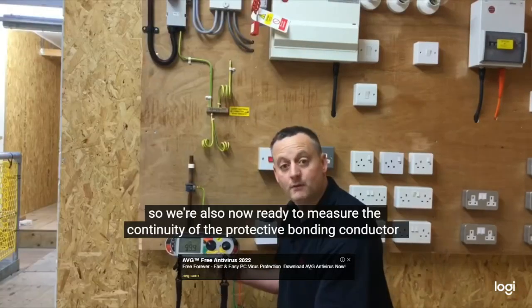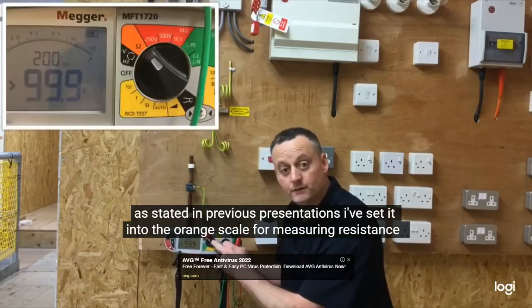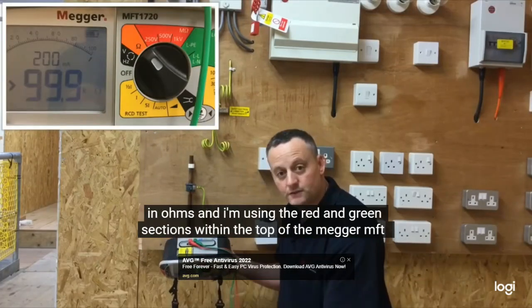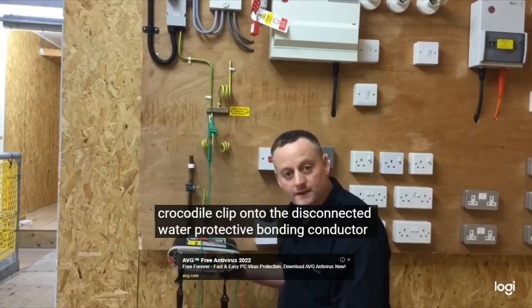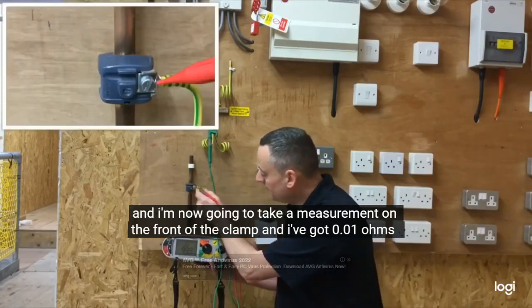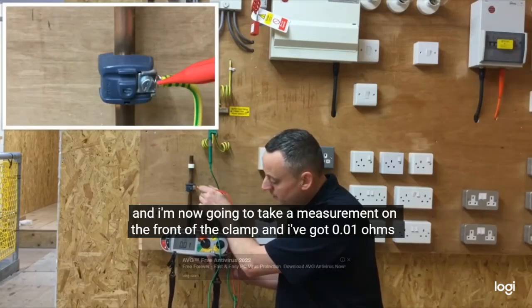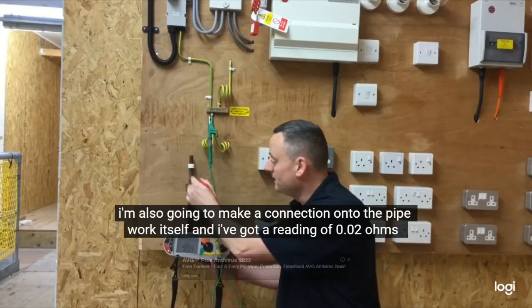Let's see how we're going to carry out the test. So we're all set up now, ready to measure the continuity of the protective bonding conductor. As stated in previous presentations, I've set it into the orange scale for measuring resistance in ohms, and I'm using the red and green sections within the top of the Megger MFT. Crocodile clip onto the disconnected water protective bonding conductor, and I'm now going to take a measurement on the front of the clamp. And I've got 0.01 ohms. I'm also going to make a connection onto the pipework itself. And I've got a reading of 0.02 ohms.